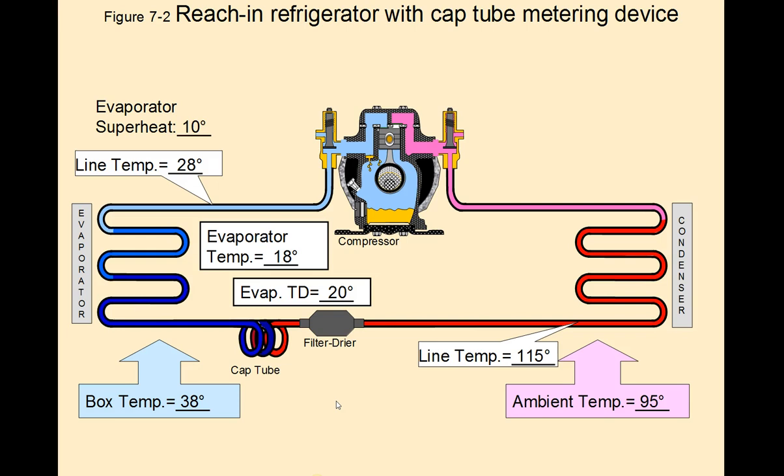And then again, the superheat is measured in the same manner as with a TXV. You're going to put your temperature probe here on the suction line at the outlet of the evaporator, and you measure 28 degrees Fahrenheit with an evaporator temperature of 18 degrees Fahrenheit. You subtract that from the 28, that gives you 10 degrees superheat.